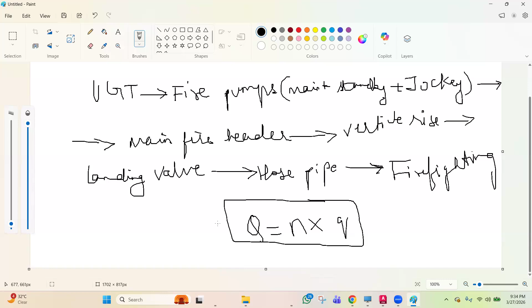For the curtain system, the discharge formula will mostly be Q equals N multiplied by small q. Here N is the number of nozzles, and small q is the discharge per nozzle, and Q is the final discharge that you get. Since all nozzles are active, the pipe carries full flow everywhere. So pipe size in a curtain system is not blindly the same; it is designed for the full flow condition. The design calculations are different, and based on them you will get the pipe size. I hope that is clear.